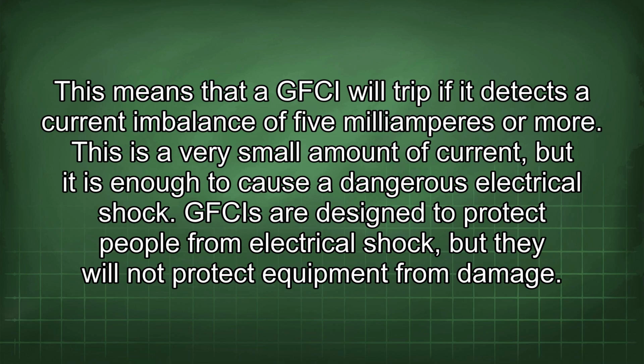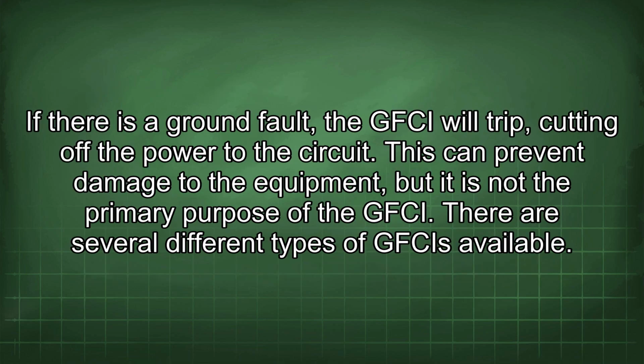This means that a GFCI will trip if it detects a current imbalance of 5 milliamperes or more. This is a very small amount of current, but it is enough to cause a dangerous electrical shock. GFCIs are designed to protect people from electrical shock, but they will not protect equipment from damage. If there is a ground fault, the GFCI will trip, cutting off the power to the circuit. This can prevent damage to the equipment, but it is not the primary purpose of the GFCI.